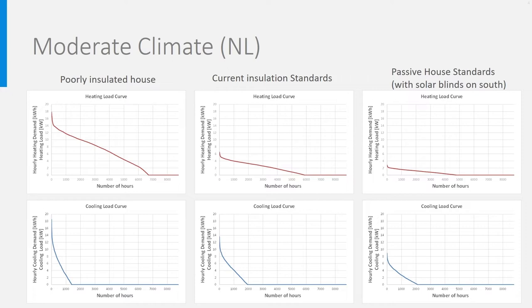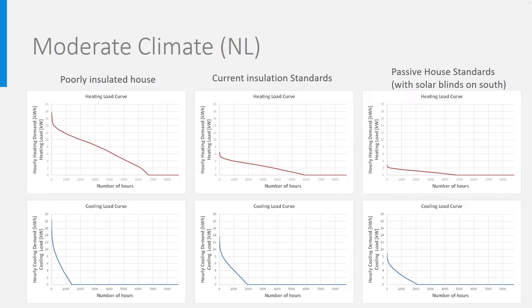As for cooling in moderate climates, we often neglect it in old houses — there is a high peak but only for a few hours per year. When insulating the house to current standards, the nominal cooling load decreases a lot but the annual cooling demand, the area under the curve, increases. The number of hours where cooling is needed increases because a considerable part of the cooling demand happens while the outdoor temperature is still quite low, and well insulated houses cannot lose the heat they gain by solar radiation. This would be even worse in passive houses, which is why solar blinds must be installed.